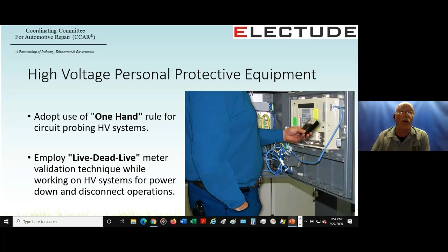A live dead live means using an alternate reference voltage to test your meter as part of the function for checking for 0 volts in things like system disconnection verification. We check the meter on the battery reference. If you're using a 12-volt battery or string 2 of them together to make 24 volts in series, we test on the reference battery and then test the high voltage circuit for 0, and then immediately move back to the reference voltage to prove that the meter is still in correct function. Live test, dead test, live test. Meter should always be tested in the same range, so you may need to shut auto ranging off on some of your squirrelier meters.